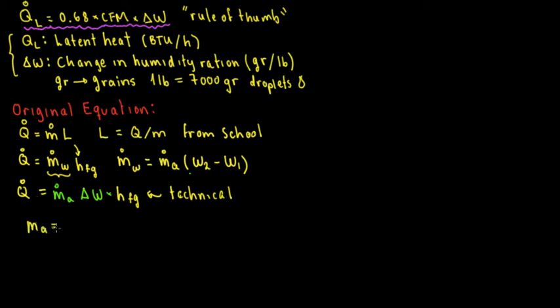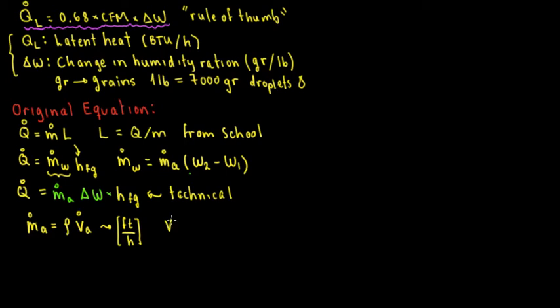Mass of air is going to be equal to density times volume of air. Since this is divided by time, this is going to be pounds per hour and cubic feet per hour. From other videos, if VA is in cubic feet per hour, then VA equals CFM times 60, because in one hour there are 60 minutes — it's just a conversion factor.